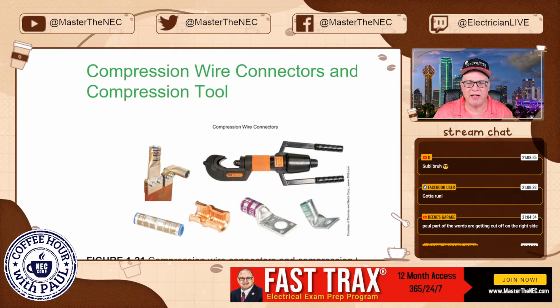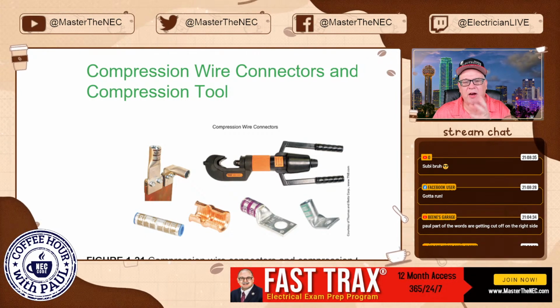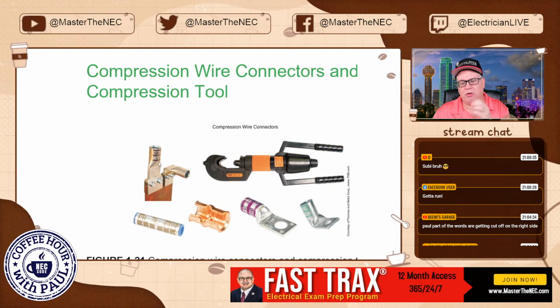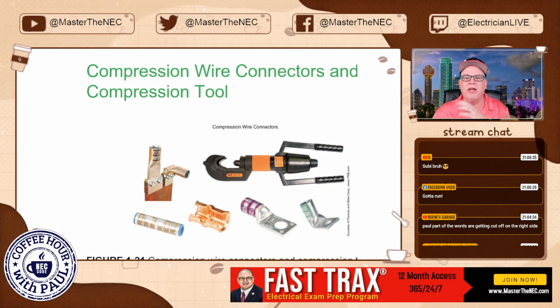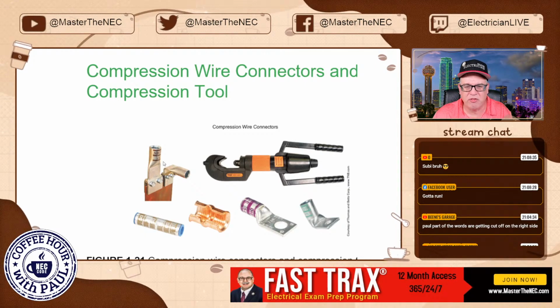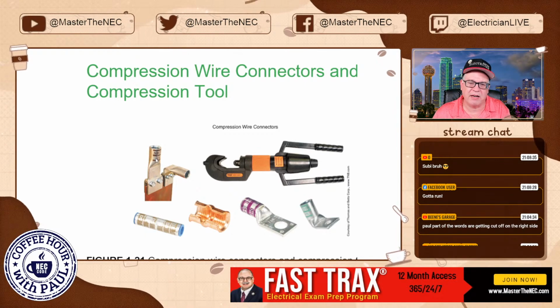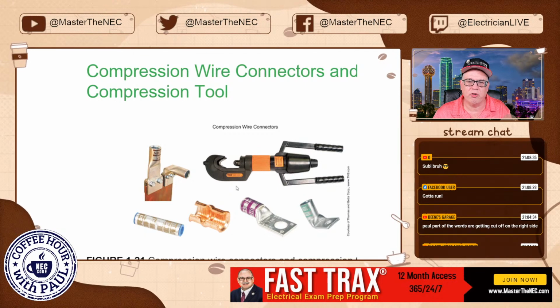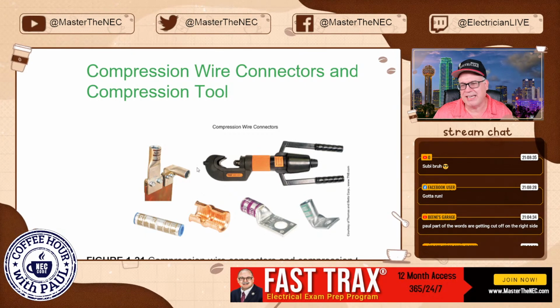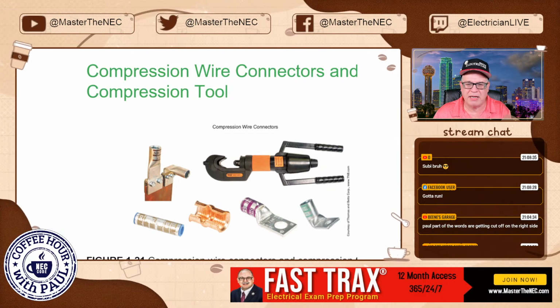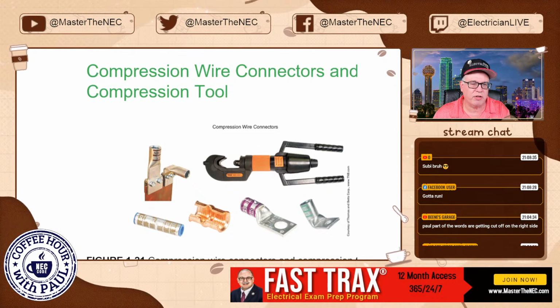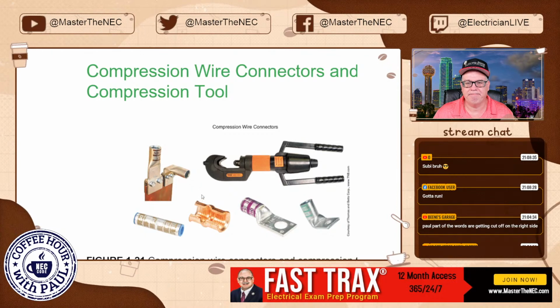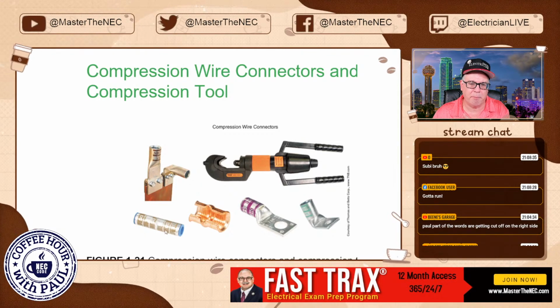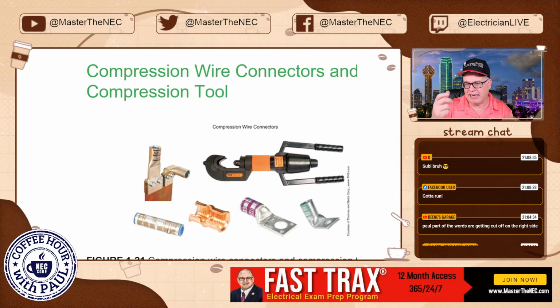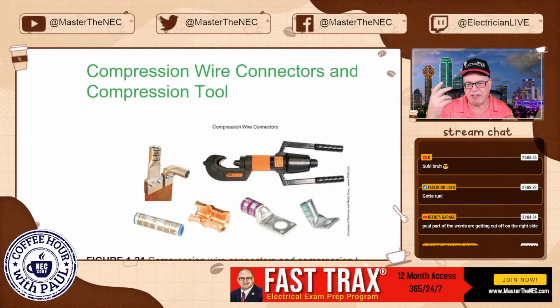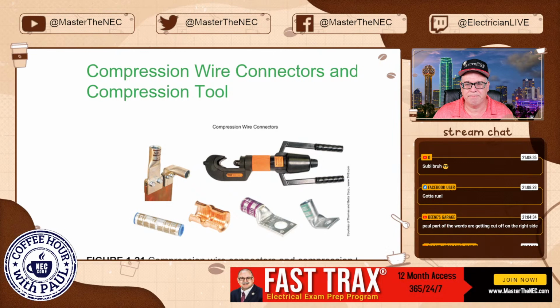So you got to do, like I said, make sure that you're putting them all in there, that you're not exceeding the number of conductors it can handle, whether it's designed for one conductor, two conductors. Make sure that's the way it is. These sometimes get pre-filled with oxide inhibitor, but just make sure you're using the proper crimping tool in order to get the job done. And usually just go to the manufacturer of whatever compression connector you're using and you'll be done. This doesn't mean you grab these here barrel splice and then you grab your side cutters and you just squeeze it tight. No, it's not what we're talking about.